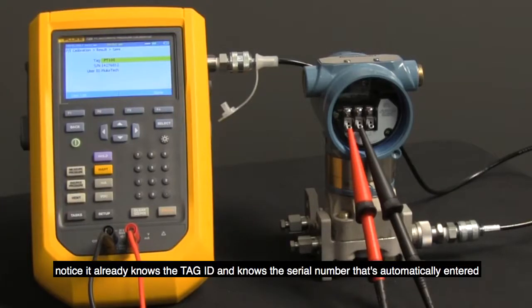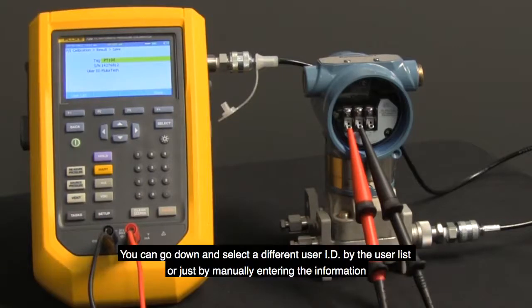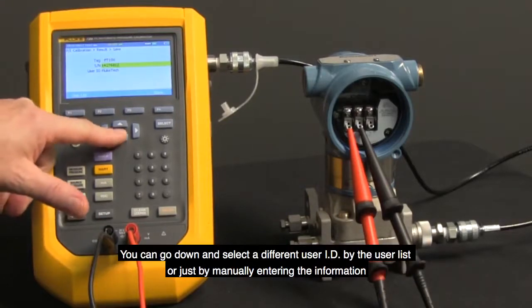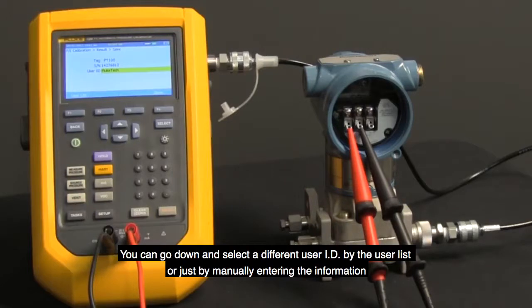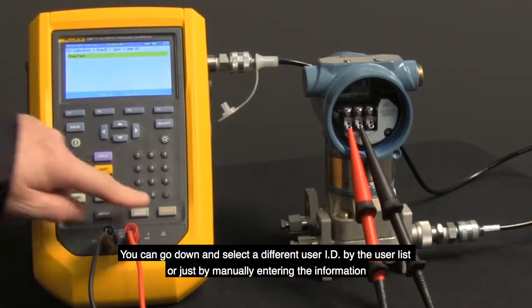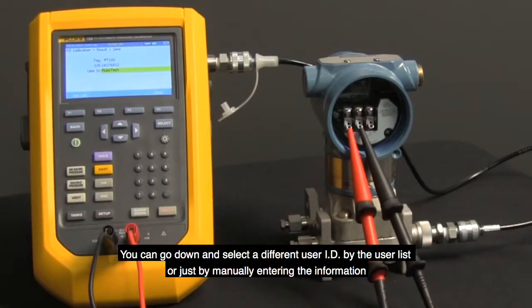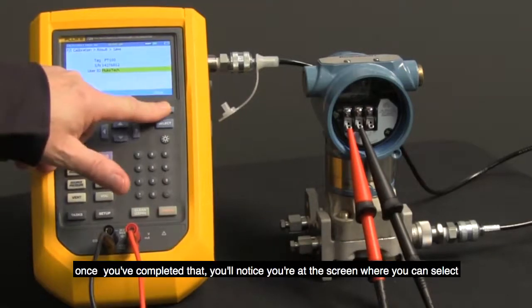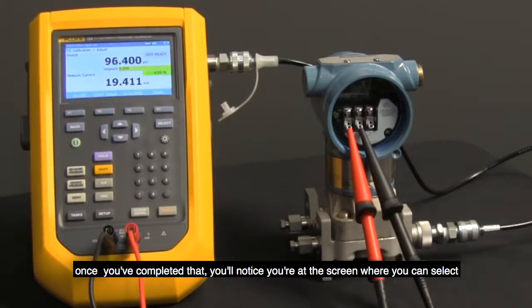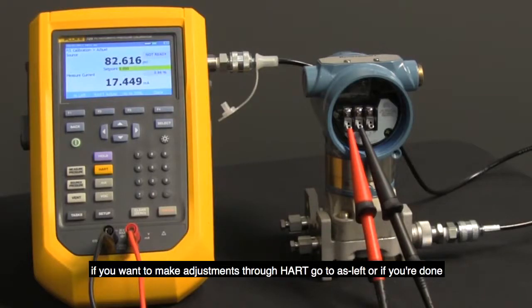Notice it already knows the tag ID. It knows the serial number that's automatically entered. You can go down and select a different user ID by the user list or just by manually entering the information. Once you've completed that, you'll notice you're at the screen where you can select if you want to make adjustments through HART, go to as left, or if you're done.